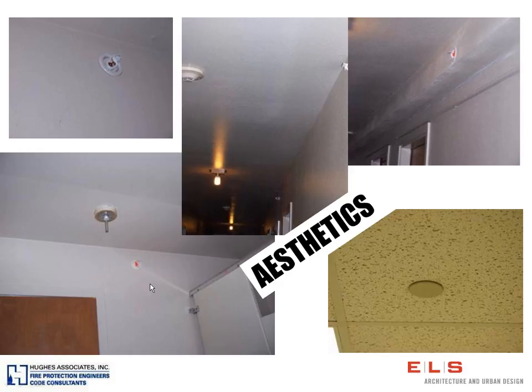In this bottom left picture, I like this picture because here's our sprinkler that's going in, and what's happening here is that this is a heat detector right here. This is a fixed temperature heat detector, and because both of these, a heat detector and a sprinkler, actuate on heat, we are now able to remove this heat detector from this bathroom. And so to me, that was a benefit, to get rid of this thing that's sticking down out of the middle of the ceiling. And the benefit here is that all this does is detect. This sprinkler not only detects, but it's also going to control fire growth or extinguish a fire.